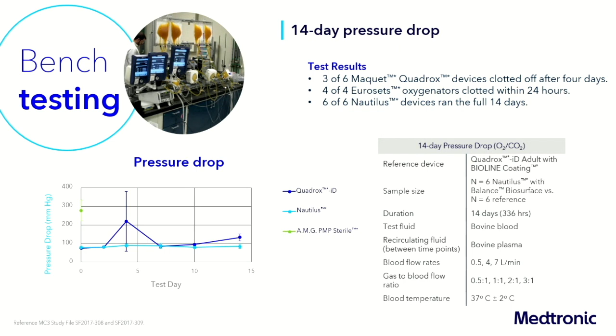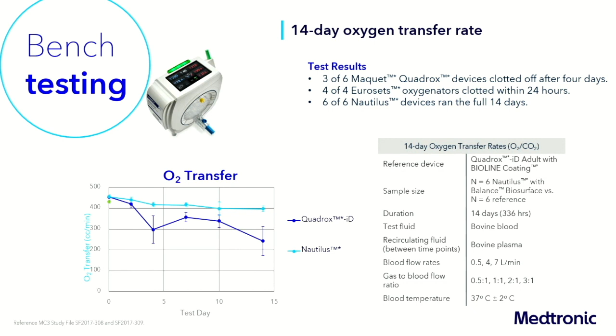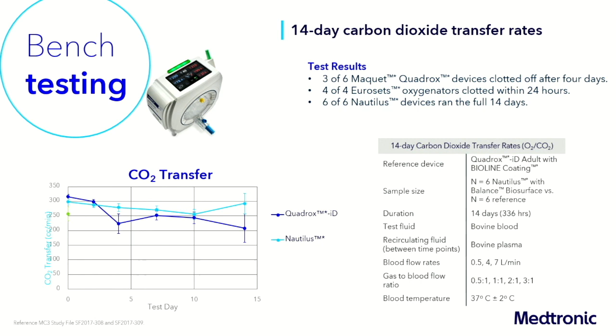And so they were able to prove that the pressure drop over 14 days stayed consistent, as well as oxygen transfer, right? So over 14 days, they ran these and measured oxygen transfer as well as carbon dioxide transfer rates. Again, looking at all of these features of the oxygenator to make sure that the device is going to provide the longer term indication for your patients.